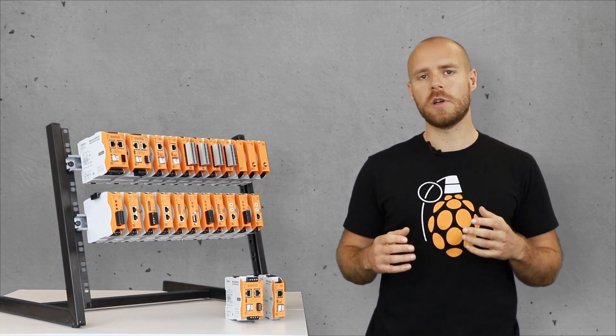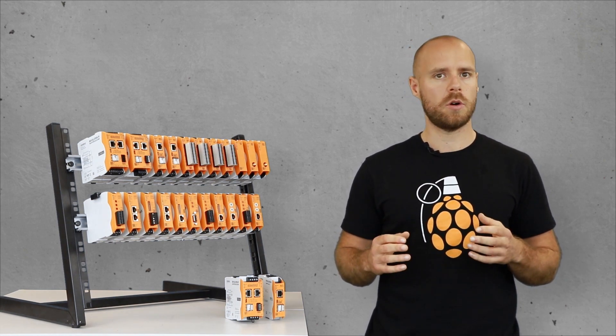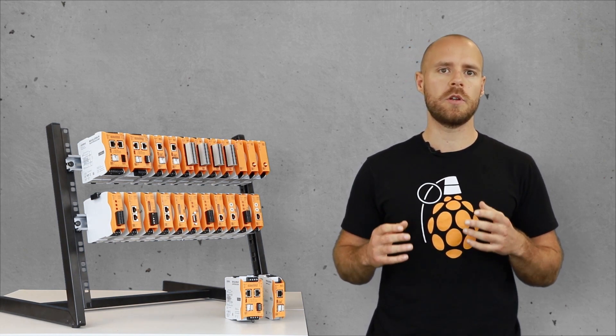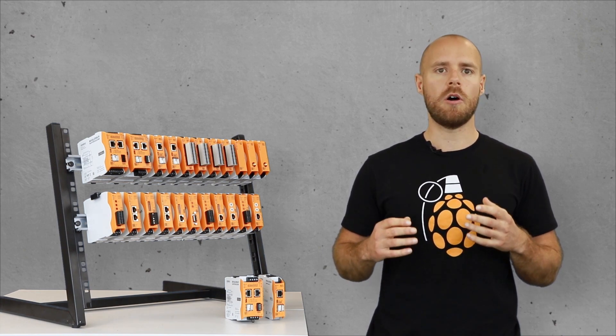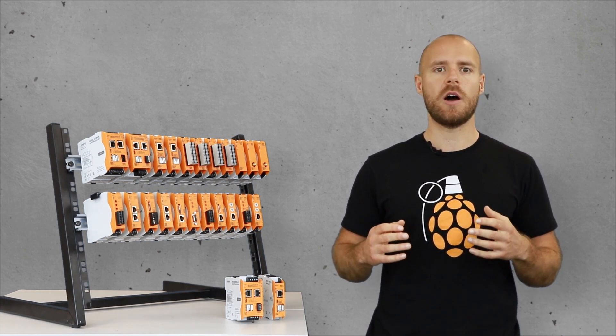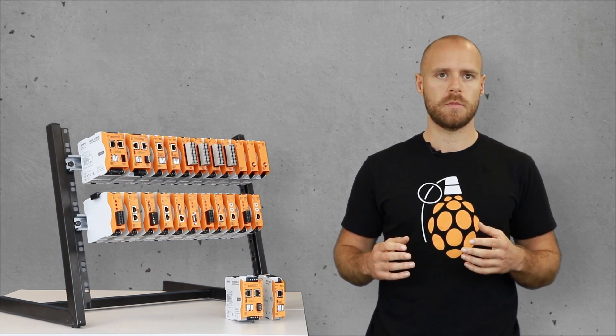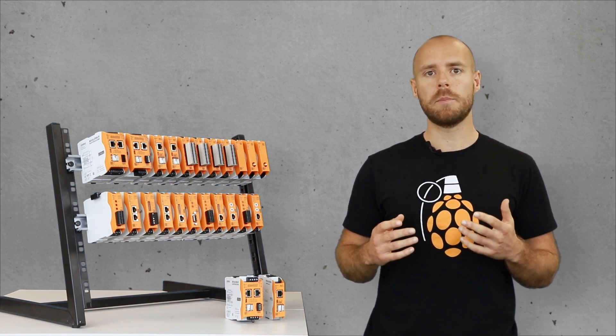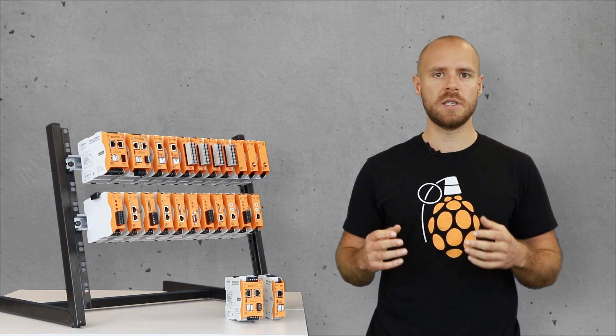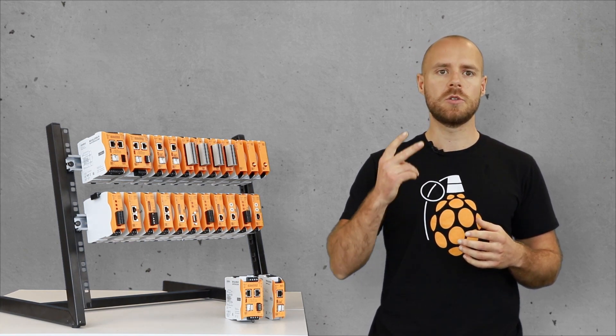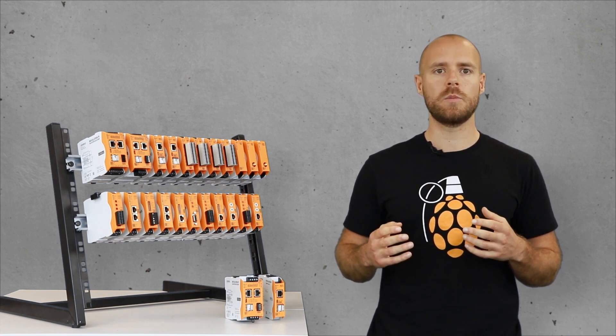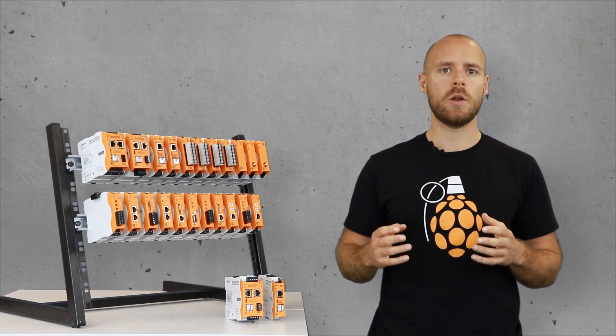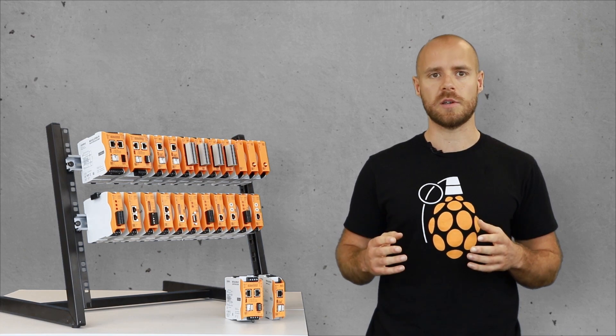While the position of the I/O modules is not important, the following should be noted for the gateways. A gateway must always be attached at the outermost module. Therefore, the number of connectable gateways per system is limited to two gateways. This means one can be equipped on the left and one can be equipped on the right side.